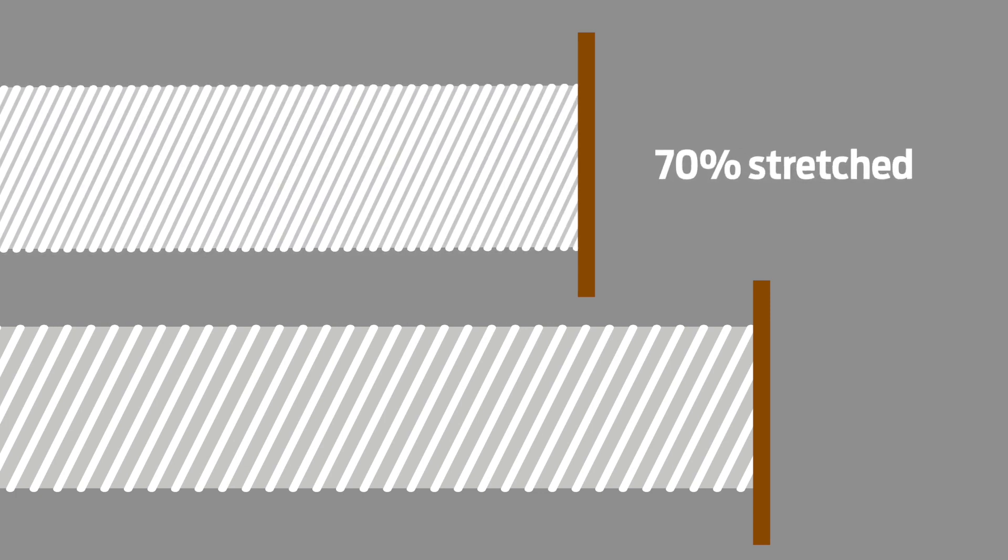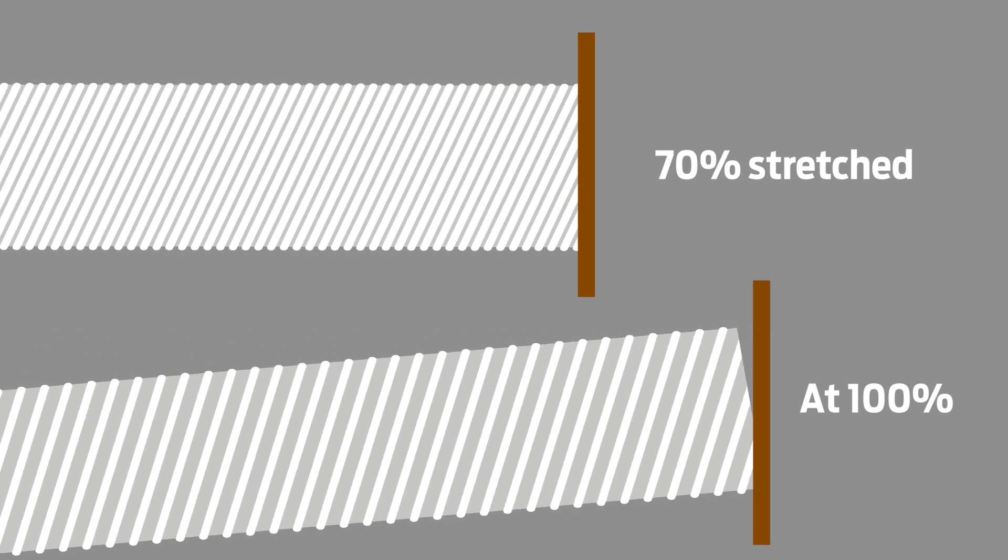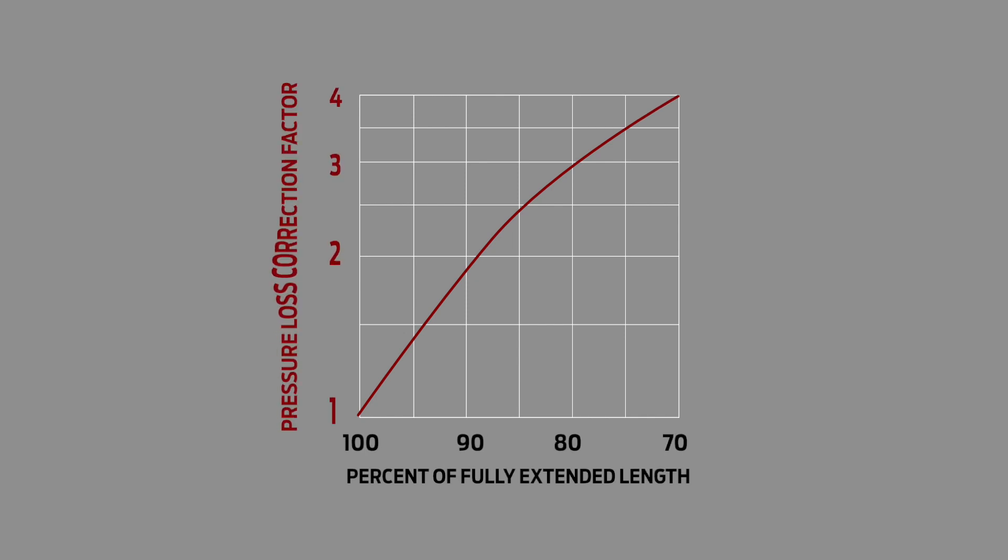In practice, flexible ducting is not still completely stretched. Understandable given that under tension it will tend to pop off grills and motors over time. This graph gives an indication of how changes in how stretched a duct is impacts on its pressure drop. Assuming best case of the ducting only being extended to 90% of its maximum length, you can see from the plot here that the pressure drop needs to be multiplied by a factor of 2. This gets worse the less stretched it is, i.e. a 70% length is a factor of 4.